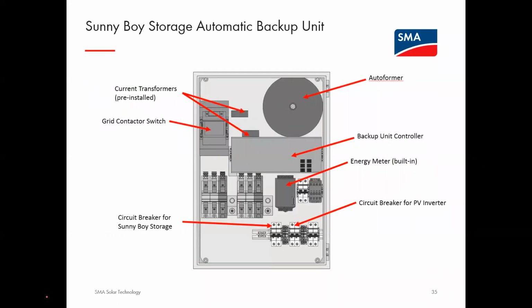In fact, what's included inside, we have a 200 amp grid contactor. This is the automatic transfer switch. We have an auto transformer built in, which is capable of balancing up to 5 kVA across line 1 and line 2 in the home, which is really important, again, for keeping a stable microgrid. Built-in energy metering: it's pre-wired and pre-installed, even the CTs are pre-installed, pre-wired, and tested at the factory, so there's really no way it can get screwed up. Also built in are 250 amp circuit breakers where you can land the output of your Sunny Boy Storage and your PV system. As I mentioned before, the AC coupled energy storage system is compatible with 100% of the PV inverters on the market. So it doesn't have to be an SMA PV inverter that you're connecting it to.